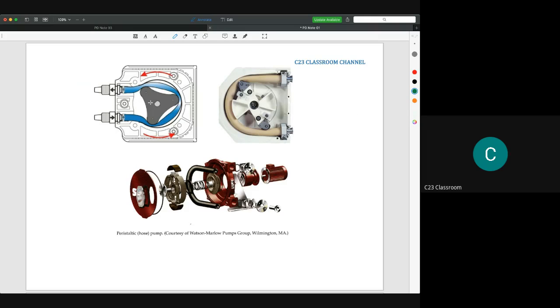Sometimes we need to use positive displacement to make sure that there is no contamination of disease in our liquid. So this pump is usually used in hospitals, especially for blood dialysis. We transfer the patient's blood from here, and this blood is moved by the idea of this one. So this is the schematic diagram.